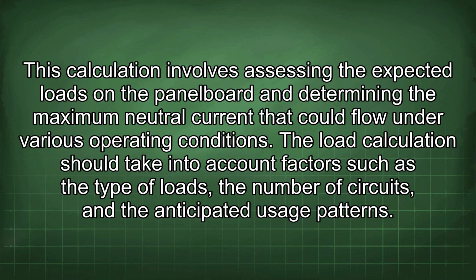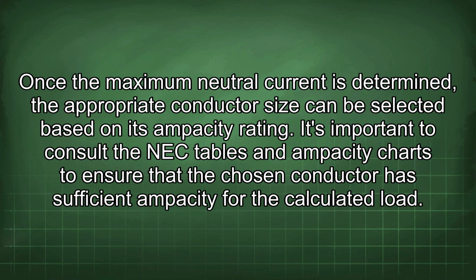This calculation involves assessing the expected loads on the panel board and determining the maximum neutral current that could flow under various operating conditions. The load calculation should take into account factors such as the type of loads, the number of circuits, and the anticipated usage patterns. Once the maximum neutral current is determined, the appropriate conductor size can be selected based on its ampacity rating.